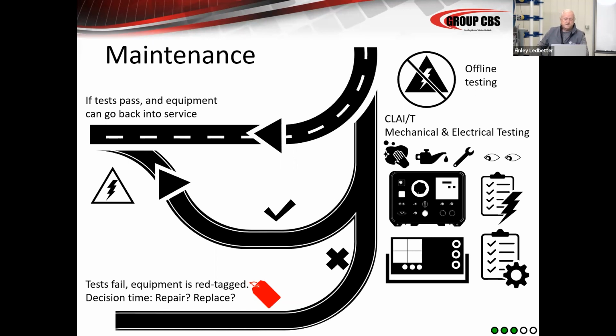Now, after this next cycle, if you don't get a red tag and the equipment goes right back into service, after 4 or 5 cycles, it's now 50 years old. You've done all the cleaning, lubing, inspecting. You've done all the electrical and maintenance tests every 5 years. Now you've been through 10 of those maintenance cycles and the equipment's 50 years old. And we're coming up upon that period on a lot of equipment right now.